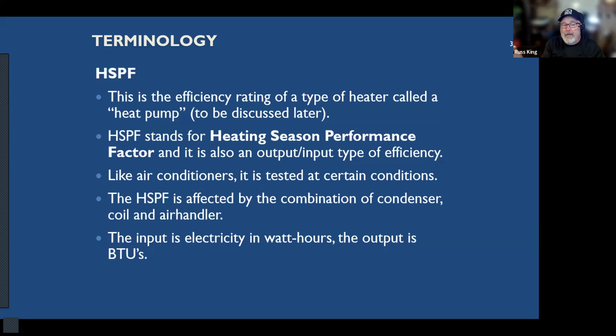So in the summertime, an air conditioner creates something cold to absorb heat and then takes it outside and squeezes that heat out. Well, in the wintertime, a heat pump is the same equipment, but it's got a little valve in it that switches direction. So now it's capturing heat from outside by making something colder than the outside. It's capturing heat from the outside, bringing that inside and squeezing that heat out inside the house. Okay. We'll talk a lot more about that. But it's electric, okay? And it's an air conditioner that runs backwards.